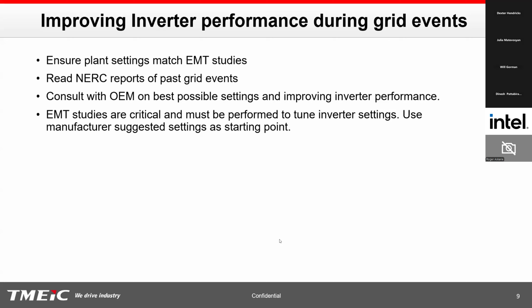So one thing that is needed moving forward is essentially to match EMT studies with the plant. And this is already happening in places like ERCOT, where a model verification report is now required to match plant settings. Hopefully this improves performance during grid events, because we have seen that if the studies don't match, the protection settings and parameters in the inverter don't reflect the EMT studies. And they have certainly caused a couple of trip events in our experience.